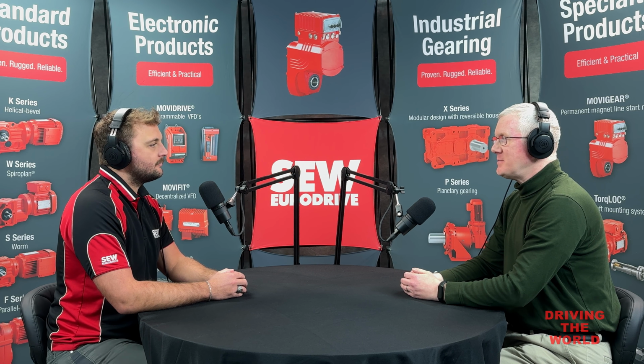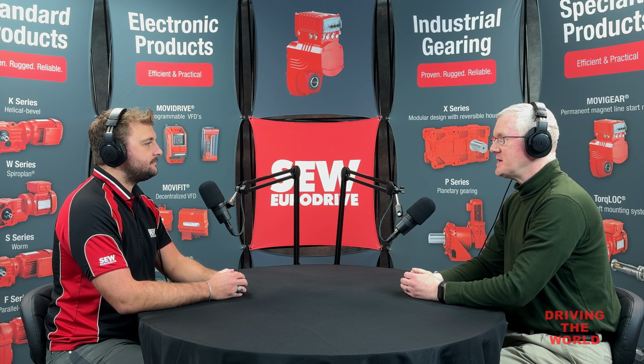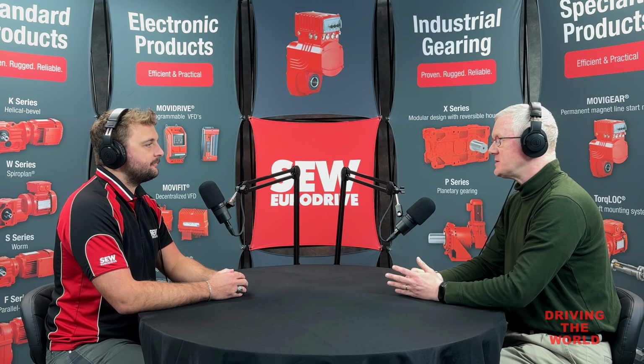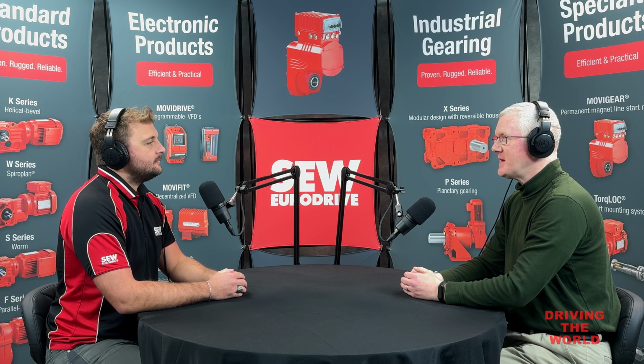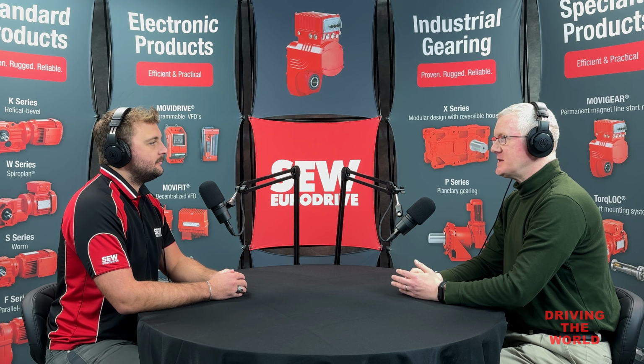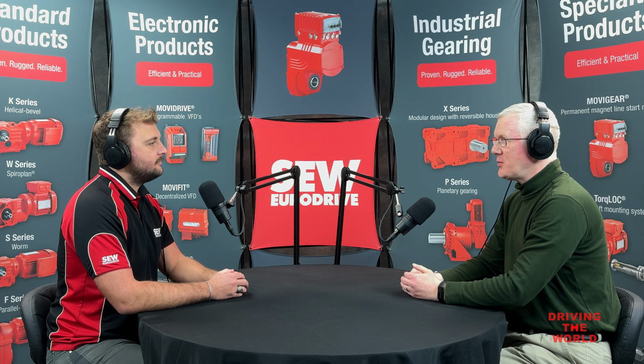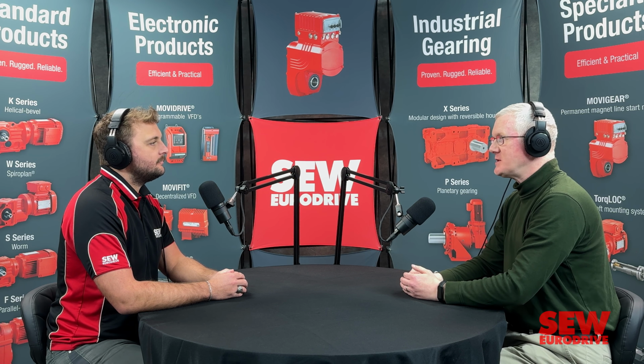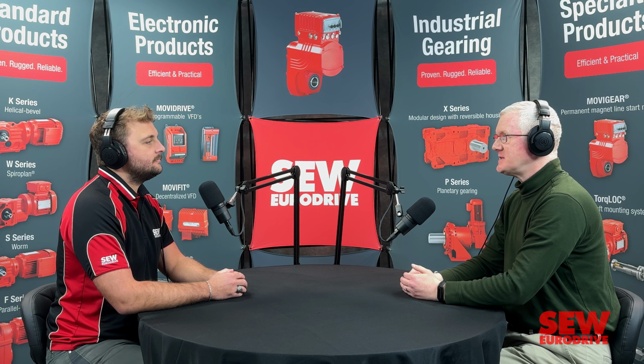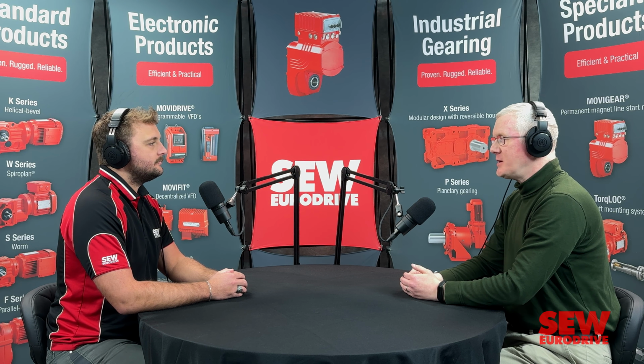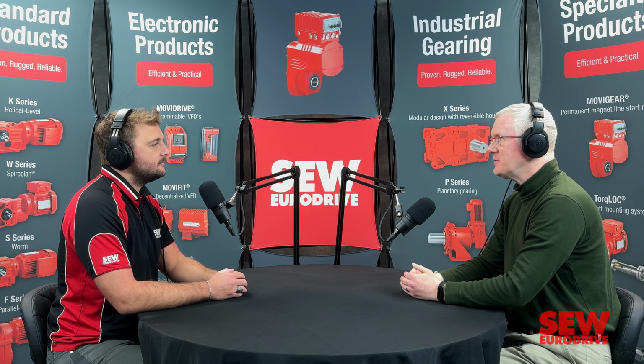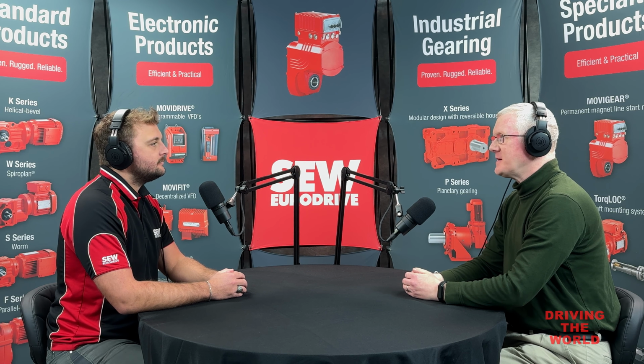And then I'll mention the new kid on the block, MoviLink DDI. This is an SEW standard we've come up with. It's a single cable motor solution, uses just one hybrid cable for everything, and carries a digital data stream from the motor to the VFD, actually multiple digital data streams. And one of those can be from an incremental encoder. So the VFD just connects to this single cable. It communicates with the motor, it controls it, and it gets the encoder information. So those are your major interfaces.